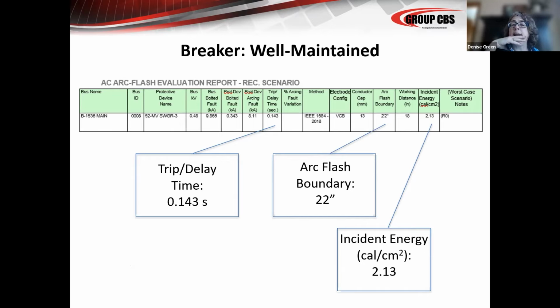Okay, so that is the 0.1 setting minimum, whichever trip unit happens to be on this breaker, that is what the setting is for instantaneous. And you can see that the incident energy at that breaker is 2.13 calories. So if the breaker is well maintained, if the breaker is lubricated, if all of those components are correct, you would anticipate this breaker to trip in 0.143 seconds, and that your arc flash boundary is 22 inches and it's 2 calories. So the electrician or technician approaching that cell and looking at that label, it's going to tell them that they need to wear either 4 or 8 calorie PPE.